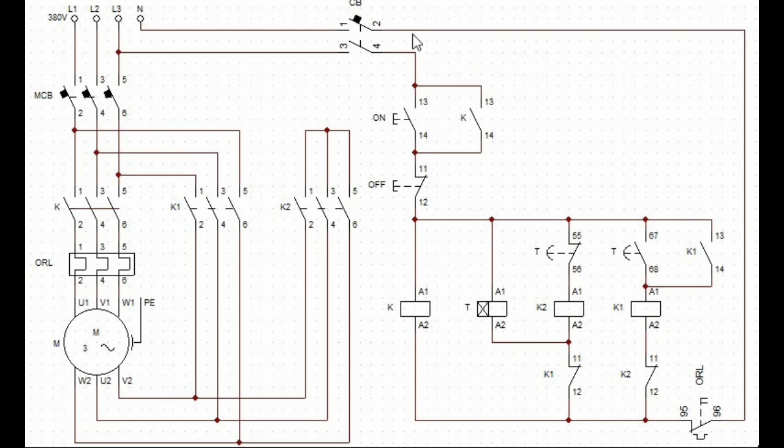The neutral line will pass through the overload, normally closed contact 95 and 96 to contactor K2 and K1, normally closed points 11 and 12. Timer coil A2 is linked with contactor K1 contact 11 to supply the neutral line.